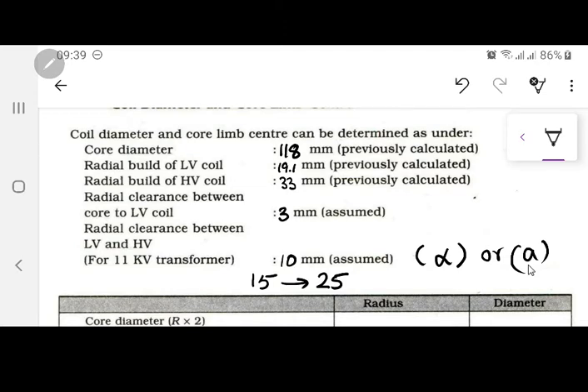But 10 mm practically is a very small distance. It's approximately just 1 centimeter, I guess. So it's not going to have much advantage here. You are going to have a little bit more heat on the hot side of the winding, because in this 10 mm gap you cannot have a lot of oil circulating. But in the R.K. Agarwal book, this distance can range from 15 mm to 25 mm. And at the end of this whole design, when we find out percentage X, supposedly you require 4.0 and it comes out to be 4.2 or 4.15.